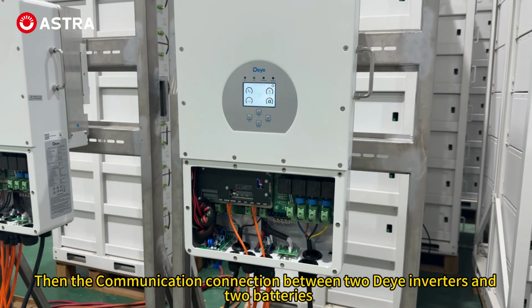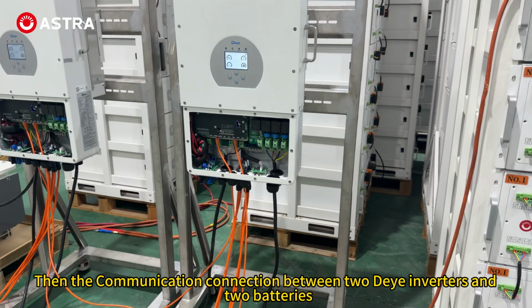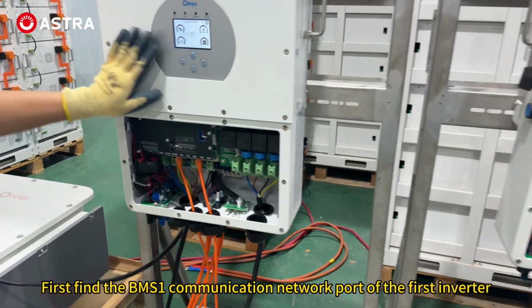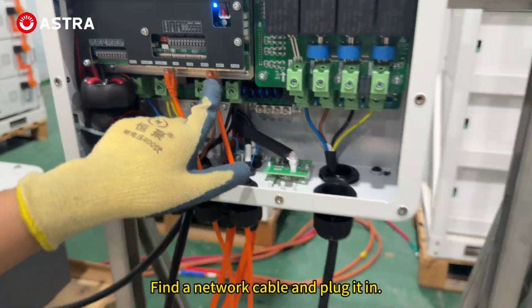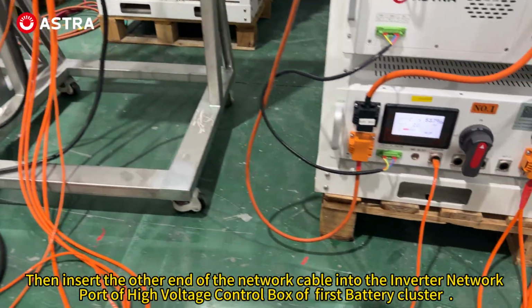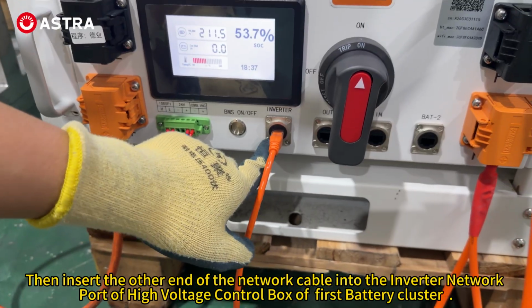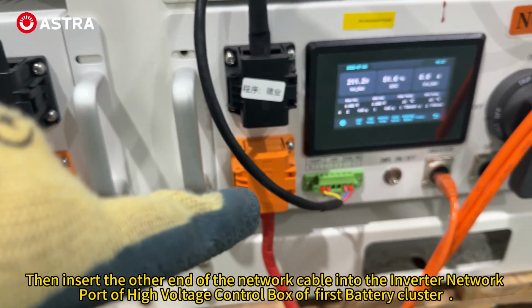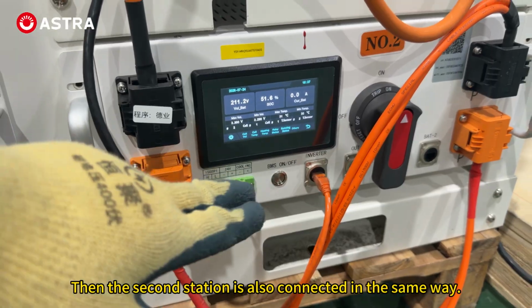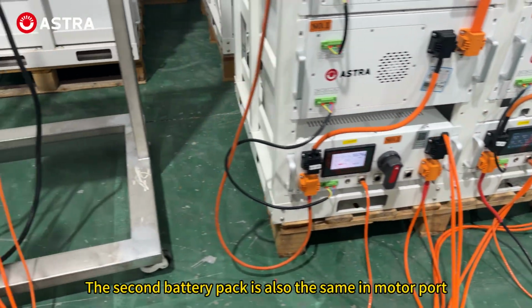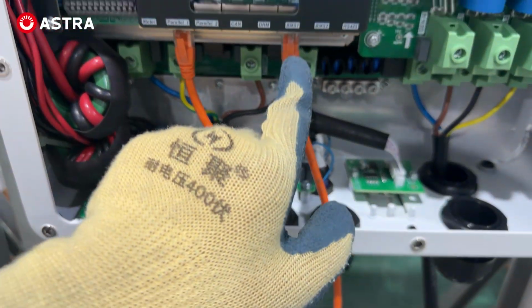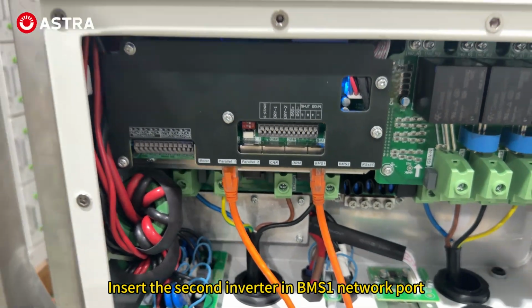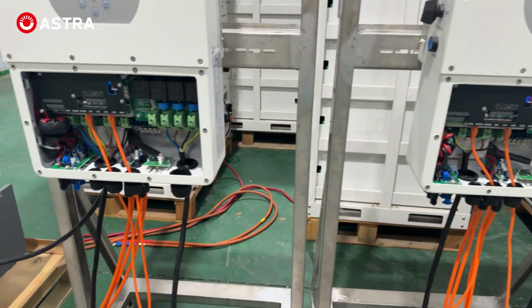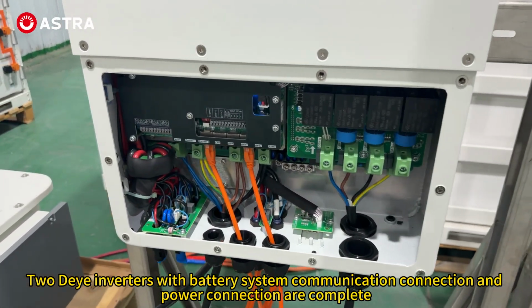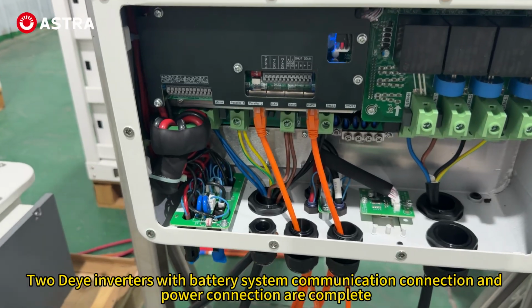Then the communication connection between the 2 inverters and 2 batteries. First, find the BMS1 communication network port of the first inverter. Find a network cable and plug it in. Then insert the other end of the network cable into the inverter network port of the high voltage control box of the first battery cluster. Then the second one is also connected in the same way. Insert the second inverter's BMS1 network port. Until now, the 2 inverters' communication and power connections with the battery system are complete.